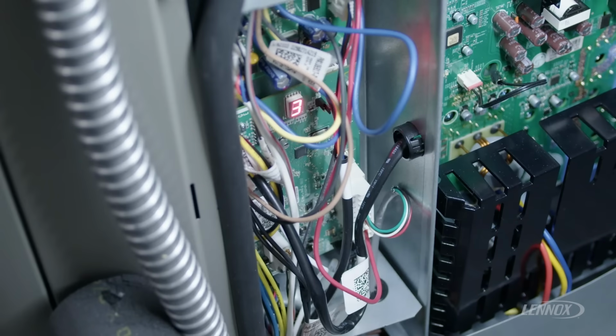Communication disruption can happen for many different reasons, but there's a very common one that's often overlooked. Our board on the left is powered by 24 volts that's provided from our indoor unit, and our inverter board is powered by 208-230 voltage that comes from our outdoor disconnect. Many times when technicians are servicing our condensing units, we turn the disconnect off outside, but fail to turn the unit off inside, which causes this breakdown in communication.